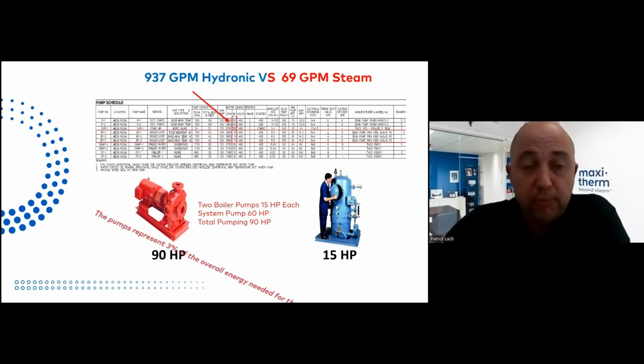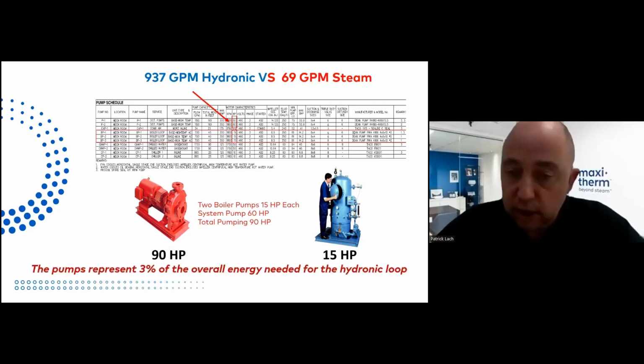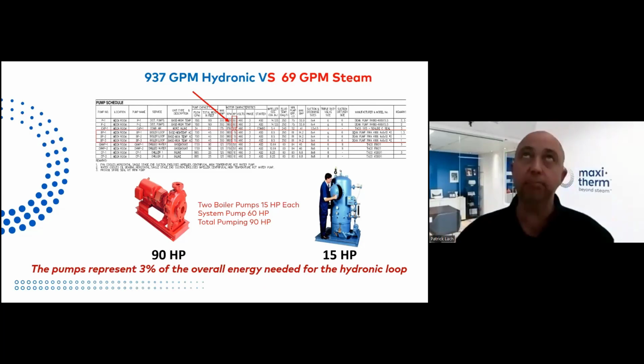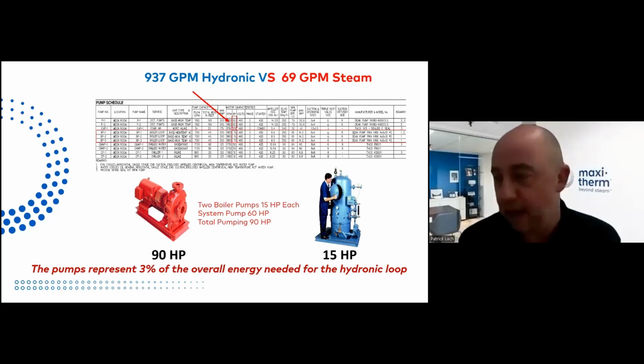And the pumps represent 3% of the overall energy needed for the hydronic loop. So a high temperature hot water boiler, if I'm not wrong, is about maximum 85% efficiency. And then you remove the 3%, you're back at 82% efficiency. Steam boiler, what I presented you earlier, we're close to 90% efficiency.